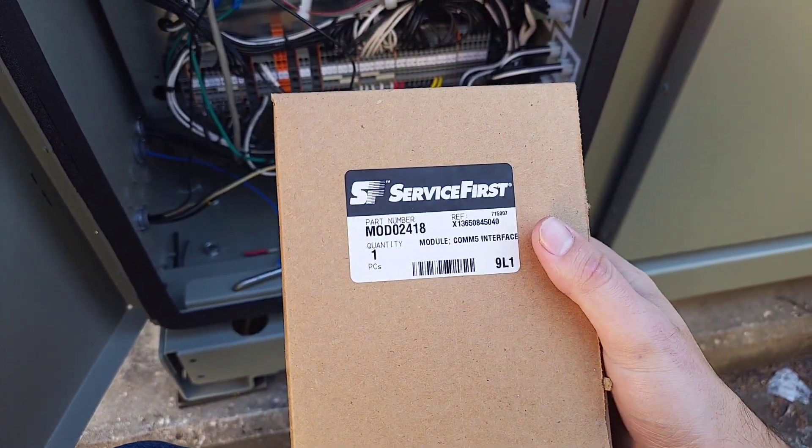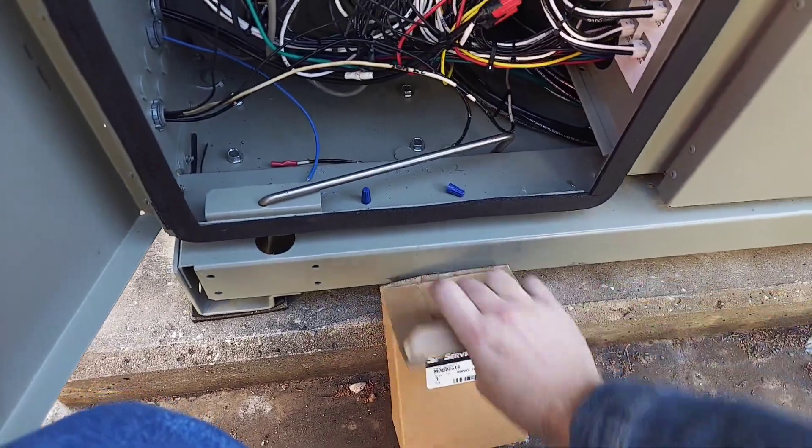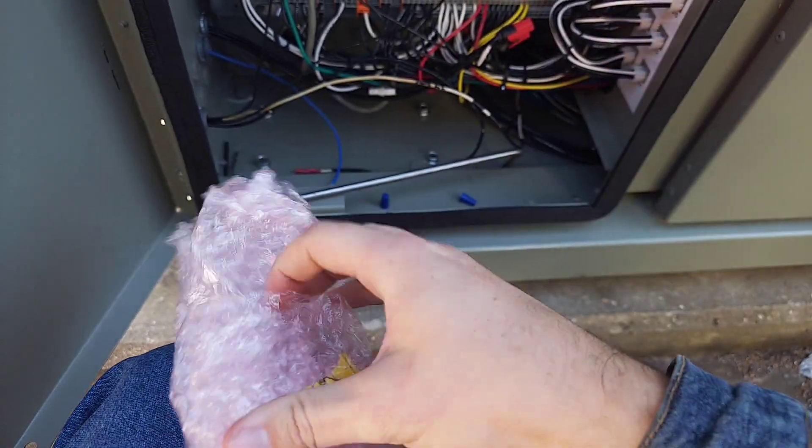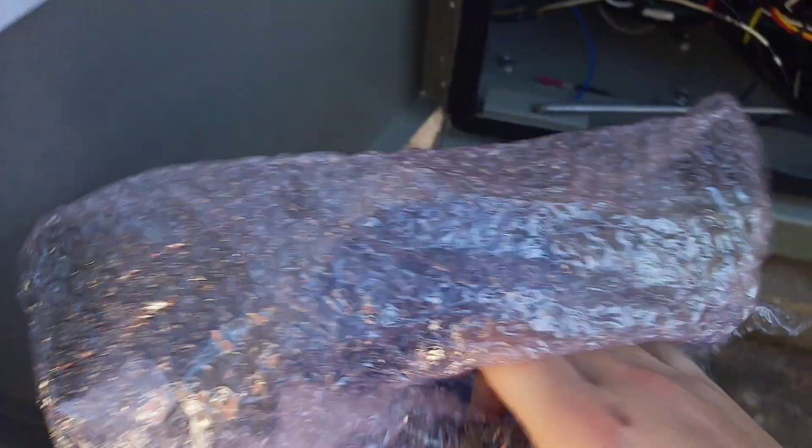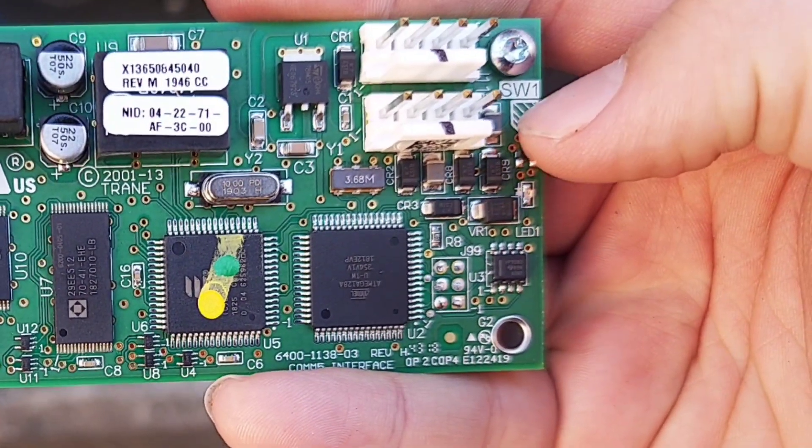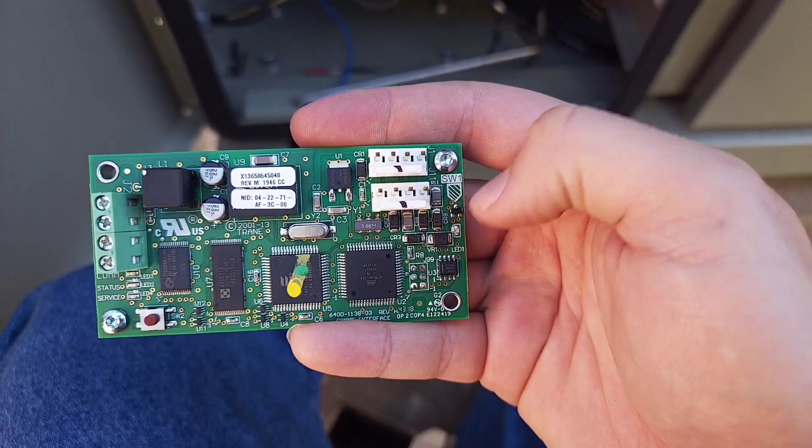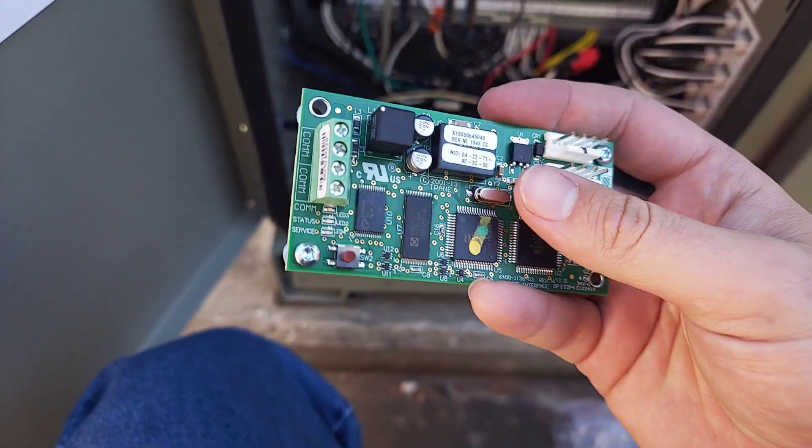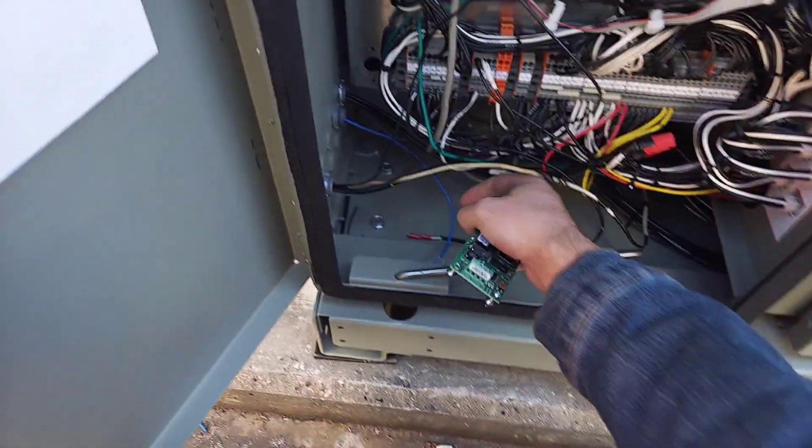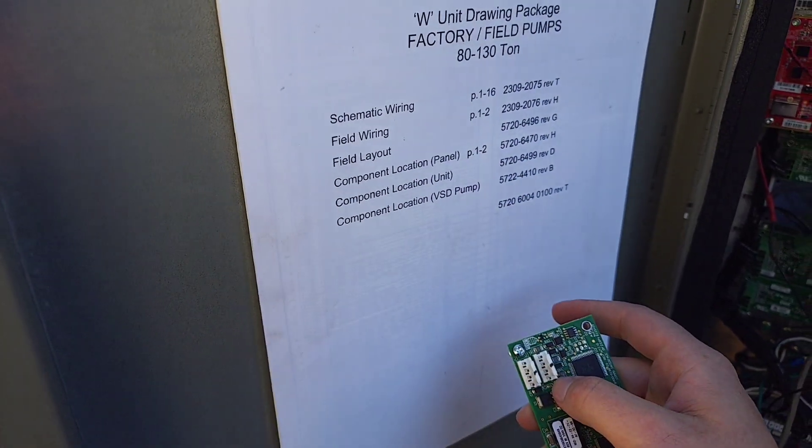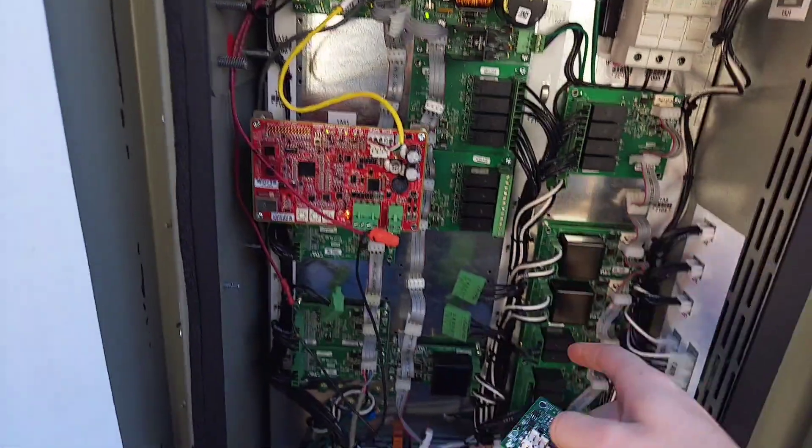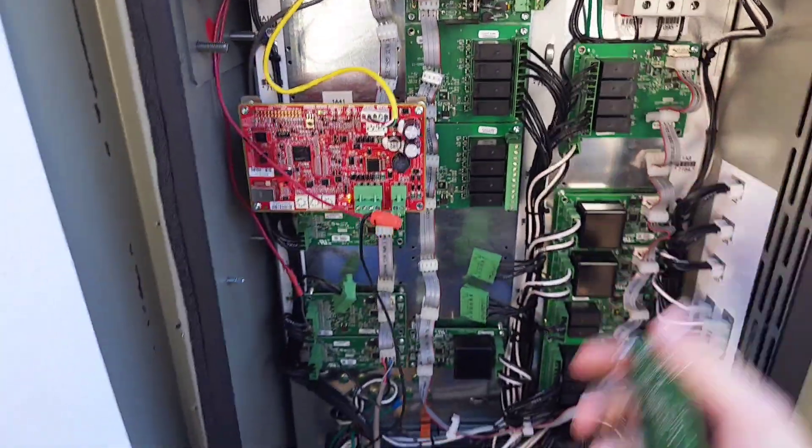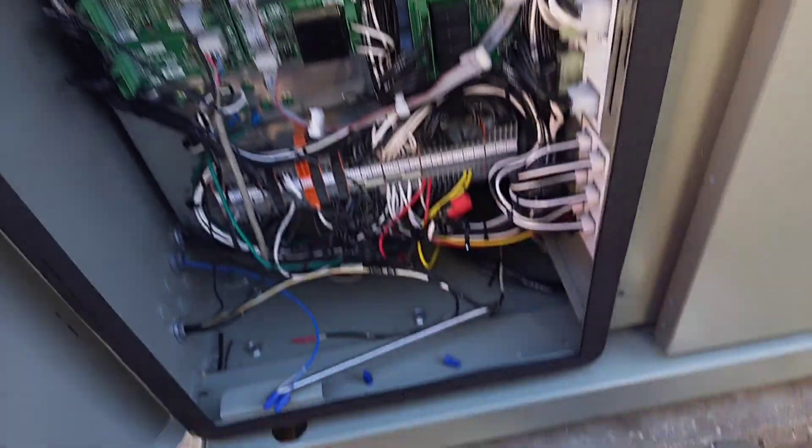There's the module, just a communication interface. We've got to get it set in and get it programmed. This will require binding because you can see right here it's got this SW1. That SW1 is an indicator. That's what we'll use with the magnet to activate this board so that we can identify it and bind it in. Then we'll get our COM wired in, which is these two wires right here going back to the automation system. I need to look at the interface here and try to verify which one of these ports they wanted this installed in.